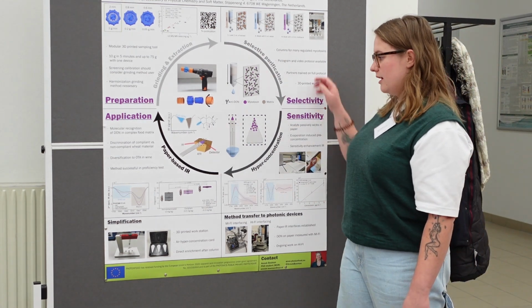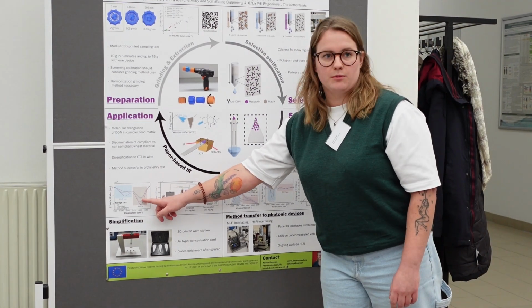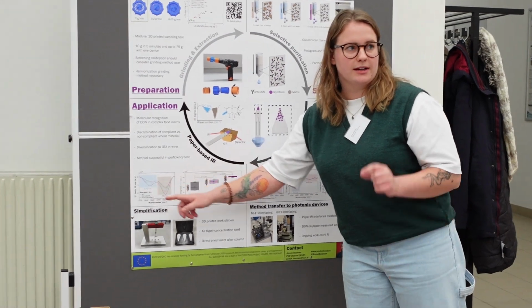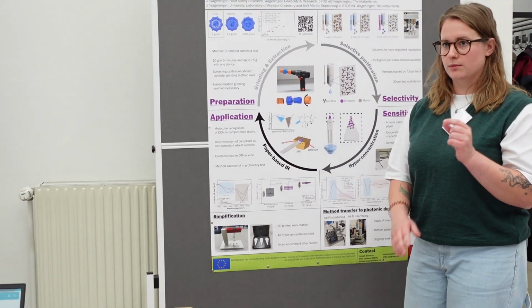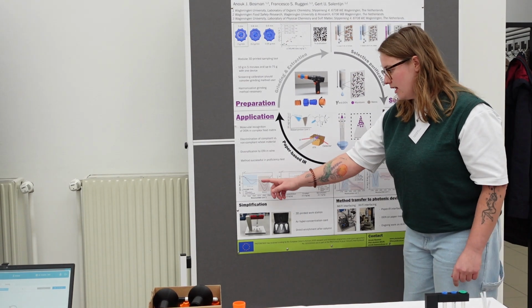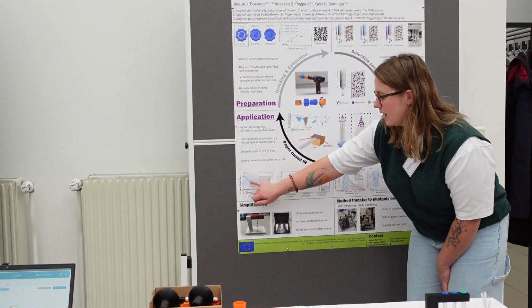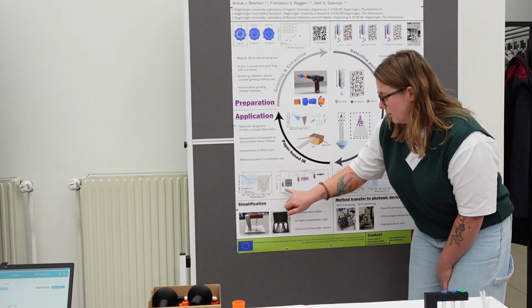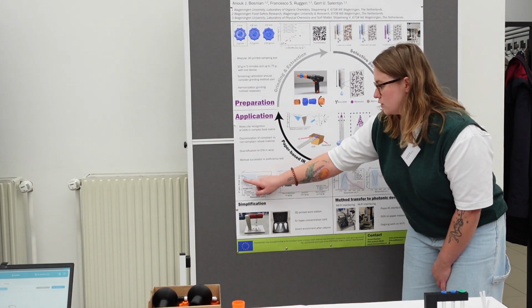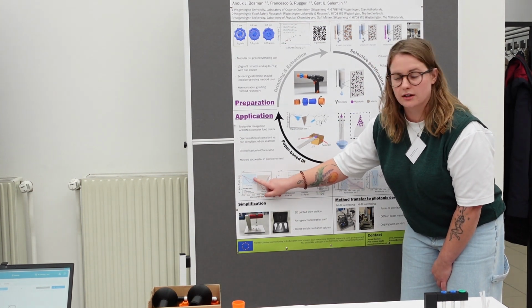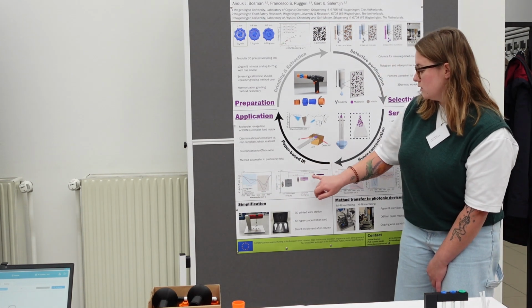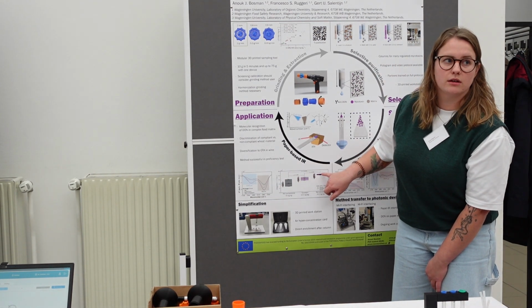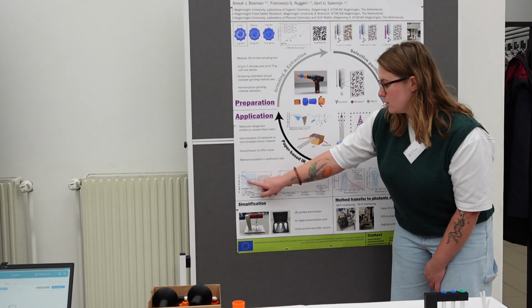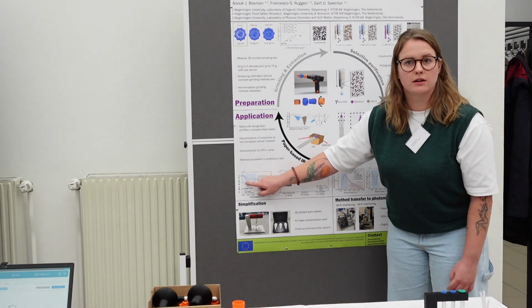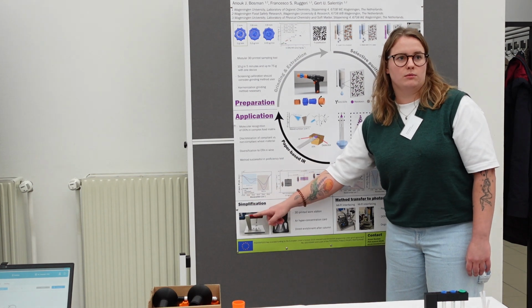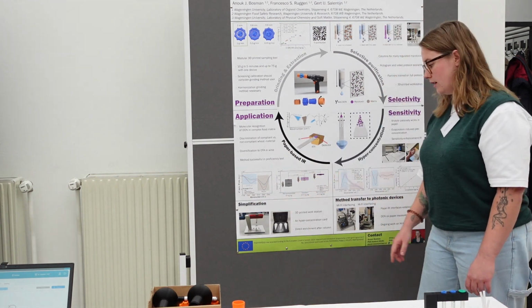Then if we do the entire method, there's always a little bit of matrix left, but still we can find back this very tiny carbonyl peak of the DON being this molecular identifier. And this is what we measure, and here the gray line is a sample that has no DON, so it shouldn't really give a peak in the second derivative, while when there is DON in there, higher or lower than the maximum set by the EU, you will see that we start to see a peak here. The more DON, the more peak you will see.